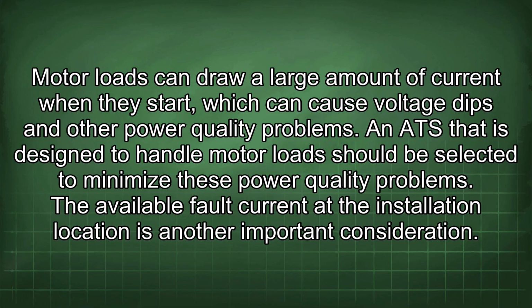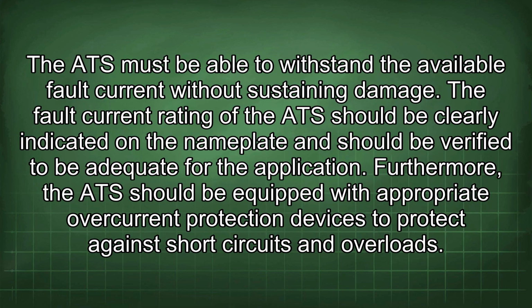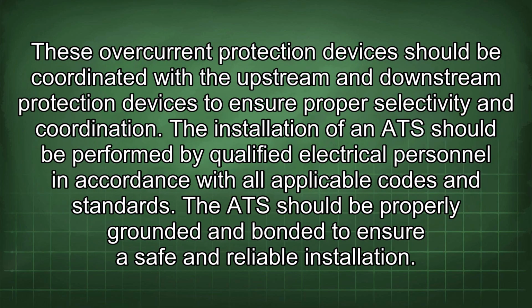The available fault current at the installation location is another important consideration. The ATS must be able to withstand the available fault current without sustaining damage. The fault current rating of the ATS should be clearly indicated on the nameplate and should be verified to be adequate for the application. Furthermore, the ATS should be equipped with appropriate overcurrent protection devices to protect against short circuits and overloads. These overcurrent protection devices should be coordinated with the upstream and downstream protection devices to ensure proper selectivity and coordination.